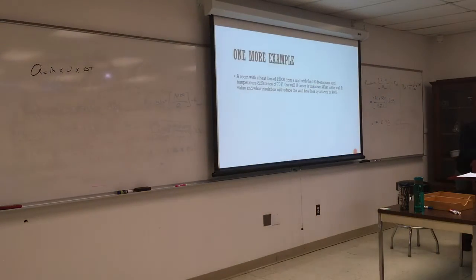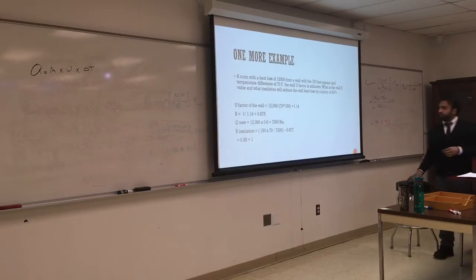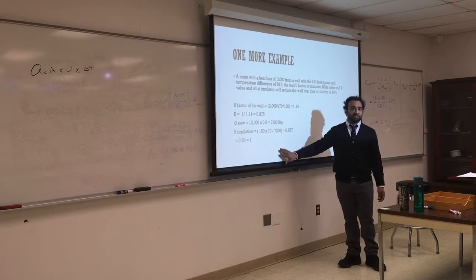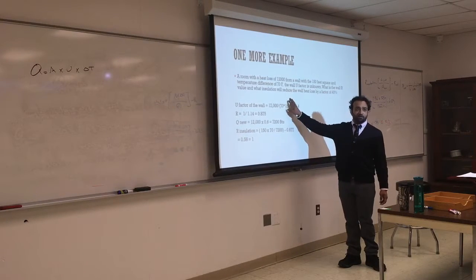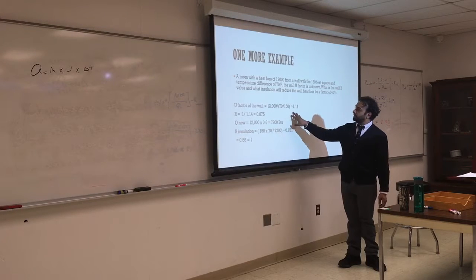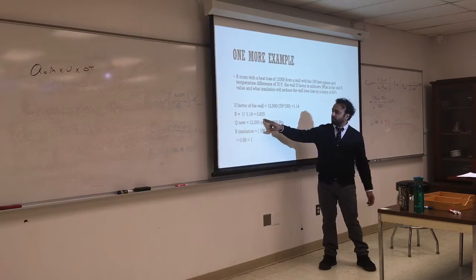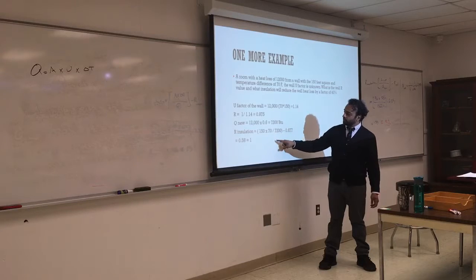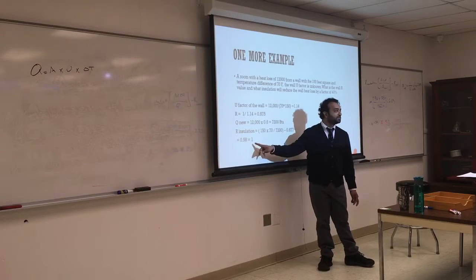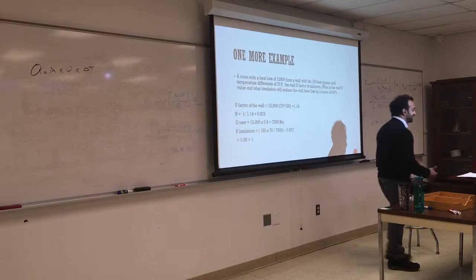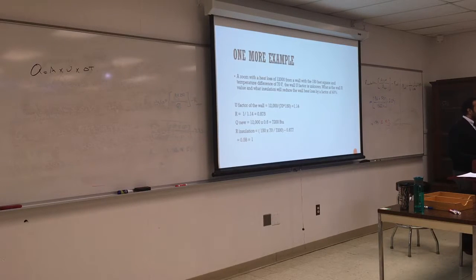So those are like 3 examples so far, and it is worked out here in detail in Blackboard. So if you get lost, you can find the steps in here. The effect of the wall, the R value, the new Q, the R insulation turns out to be 0.58, so you just go up to R1, which is not a lot. So in this case, with insulation, you would round up instead of rounding down, because you're not gonna find 0.5. You're gonna go with 1.